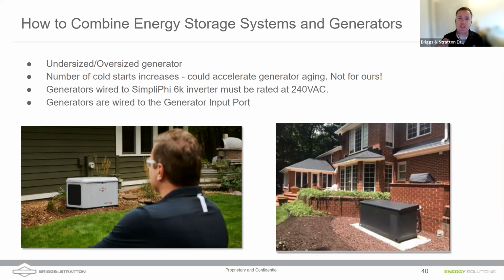Number of cold starts, I've got this coming up: what we're doing now is telling the generator to start up and shut down, start up and shut down. Is that going to wear out the engine? Not in our case. Why? Because the engine inside of our generators is used in a lot of lawnmowers, a lot of light towers, and a lot of other applications where that engine is designed to be started and stopped repeatedly without damaging it.